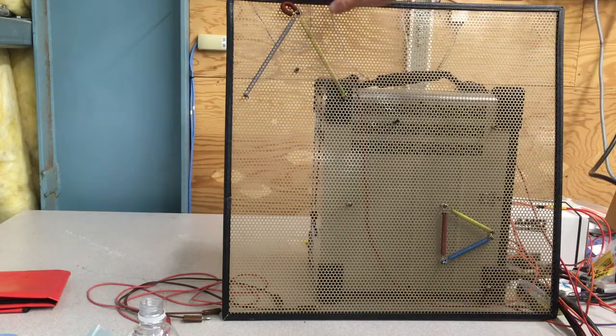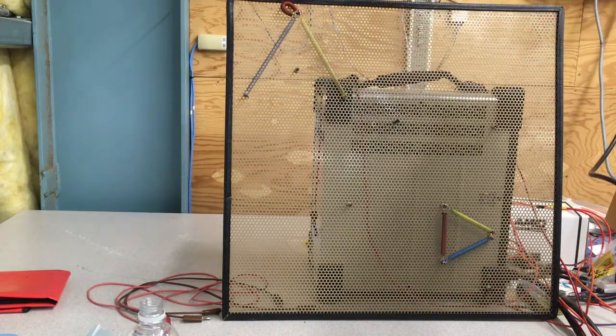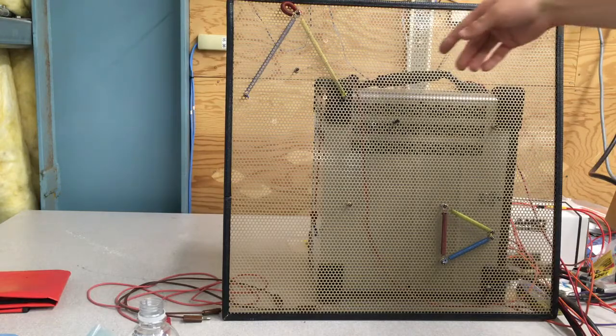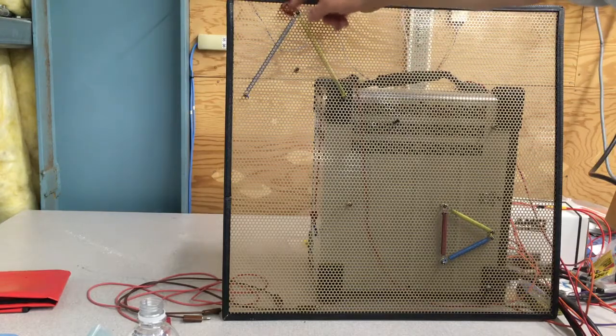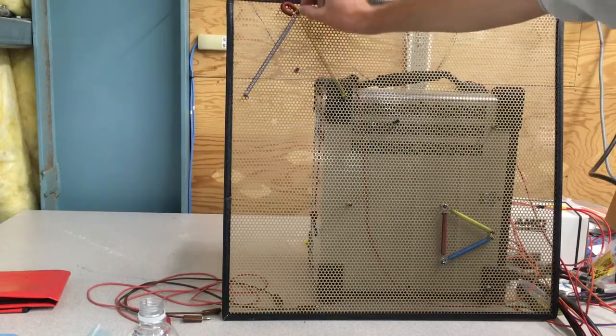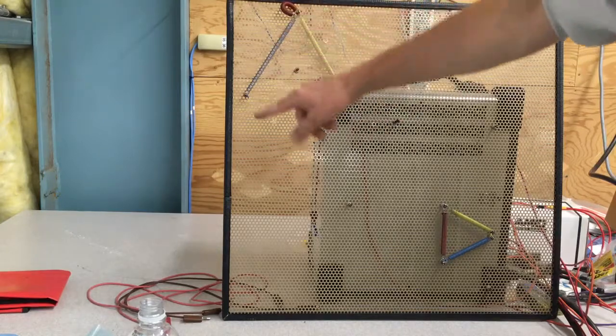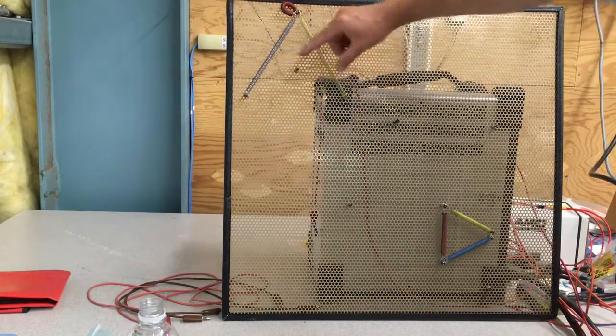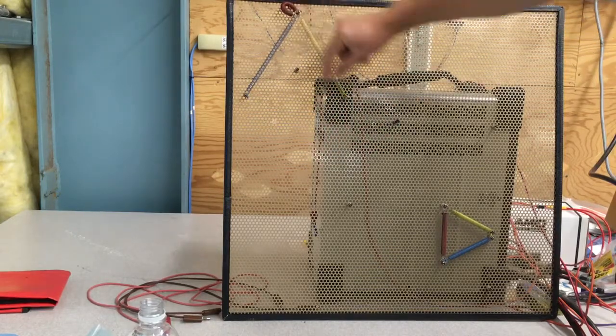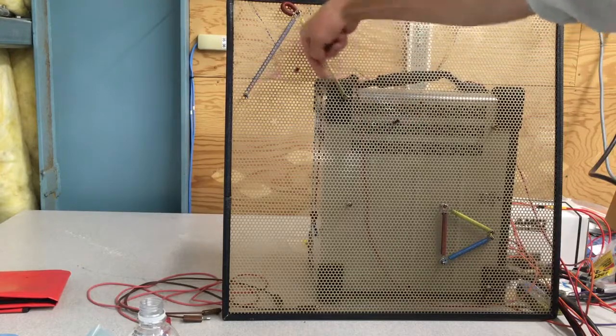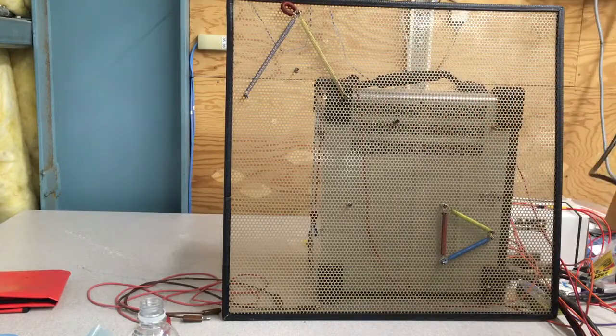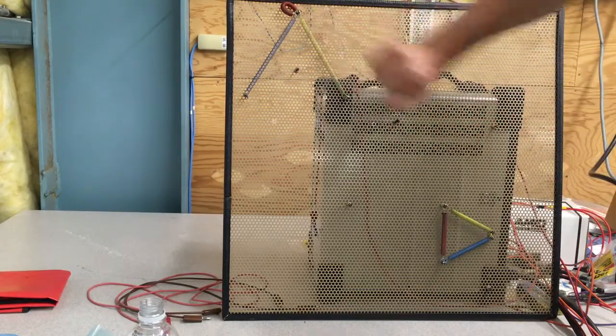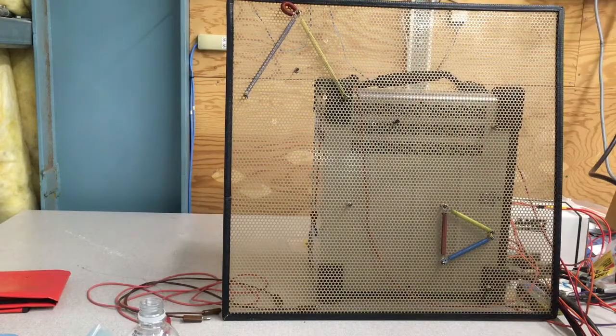It doesn't care that there's just a phase to ground fault because it's a delta system. So you'll see that the A phase winding gets shorted. The B and the C phase are now at a 60 degree relationship to each other instead of 120 degree relationship to each other, and the magnitude is increased by the root of 3.